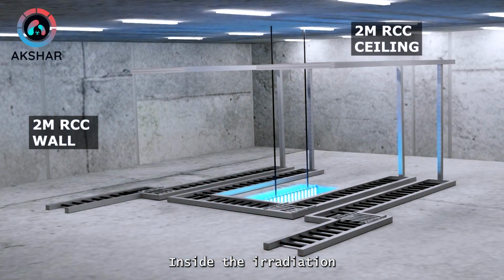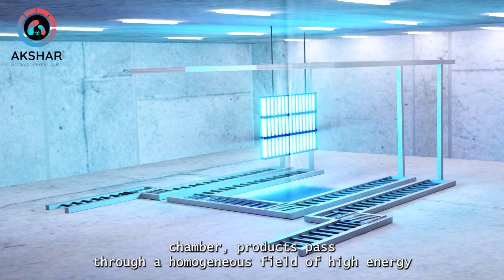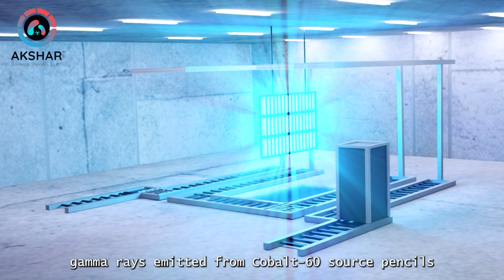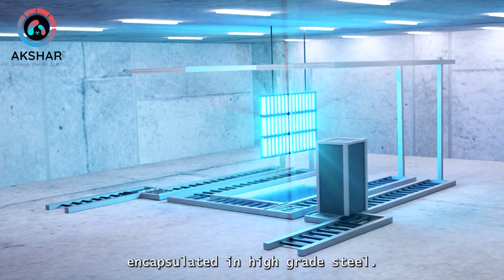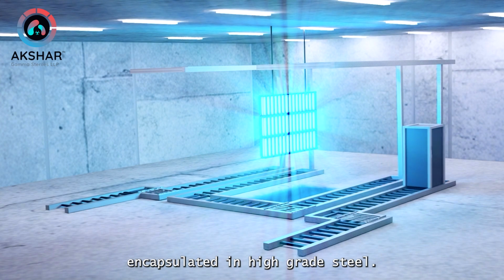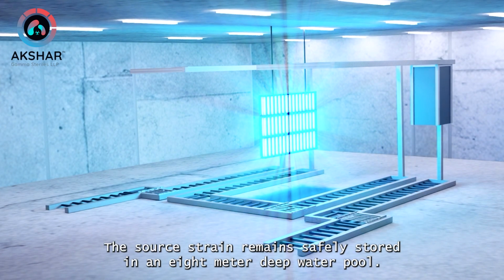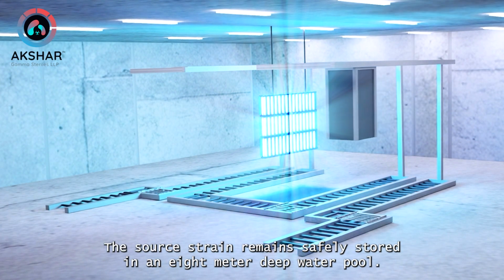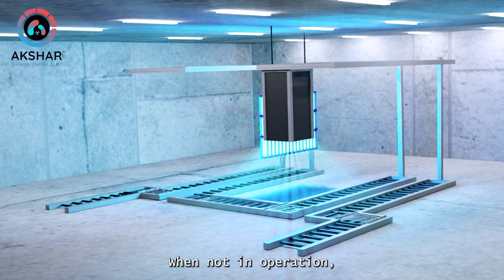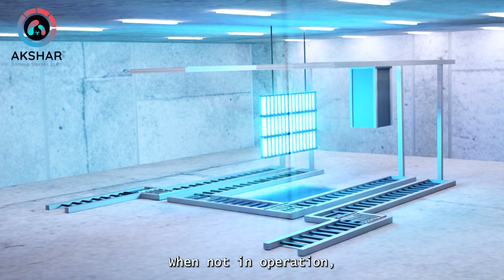Inside the irradiation chamber, products pass through a homogeneous field of high-energy gamma rays emitted from cobalt-60 source pencils encapsulated in high-grade steel. The source frame remains safely stored in an 8-meter deep water pool when not in operation.